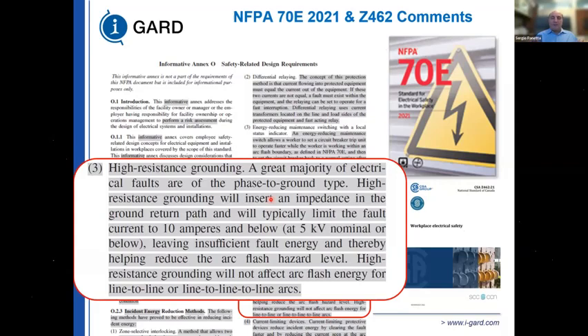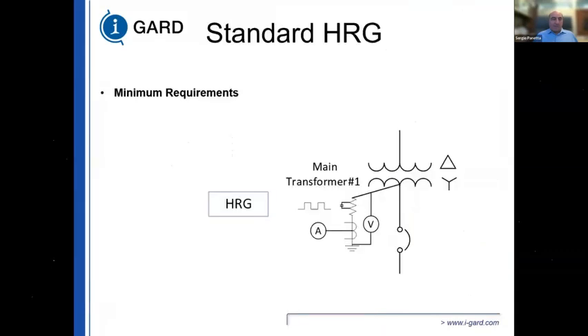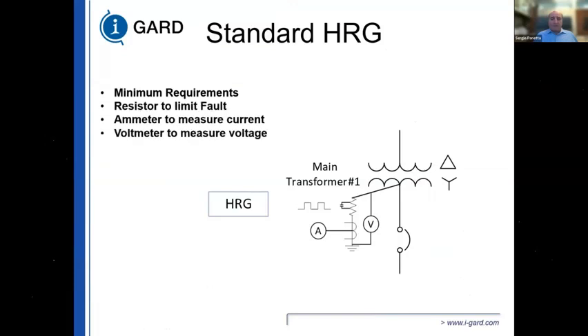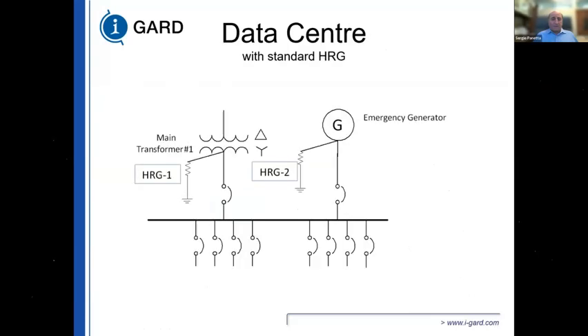All it does is reduce the likelihood of exposure by limiting the fault current to a low value, whereby the ground fault will not propagate to a phase-to-phase fault and create a three-phase fault. This is on systems up to 5,000 volts, 5 kV. If you limit the fault current to 10 amps or less, you have an arc flash mitigation technique. So a standard HRG system, the minimum requirements are resistor to limit the fault, ammeter to detect the current, voltmeter to measure the voltage, pulsing contactor.